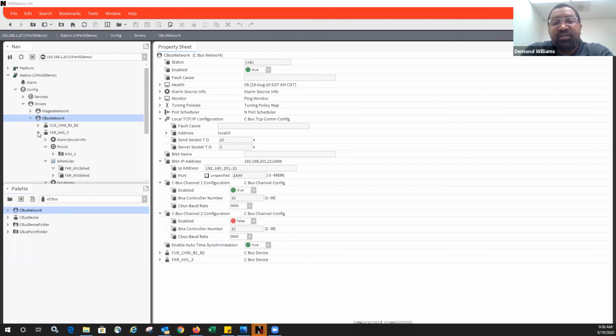When you plug it into the bus network, you can put it at the beginning, you can put it at the end. If you do either one of them, you have to make sure you put a 120 ohm resistor on it. But Honeywell's recommendation is basically putting it in the middle of the network or anywhere on the network. And then once you get it on the network, your transmit and receive lights will automatically pick up. Once those start communicating, then the Clif controller is ready to go.